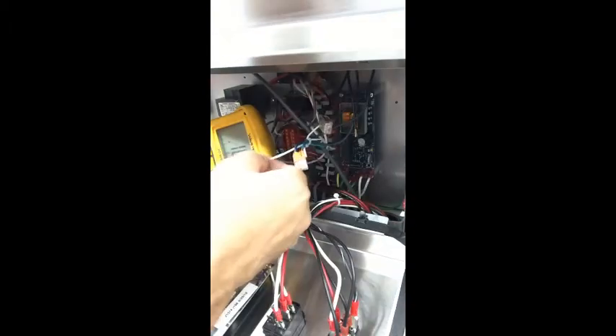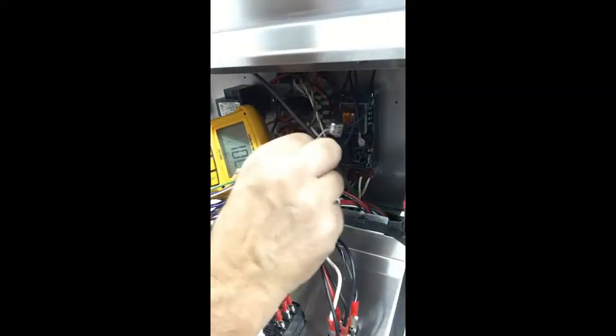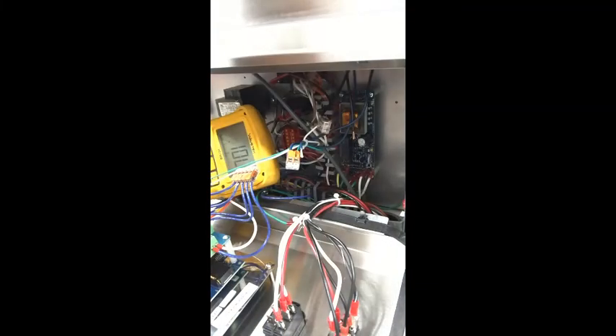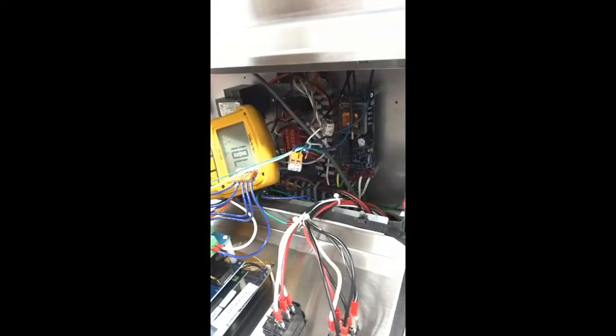Okay, so we're coming out on the green, hitting our blue wire, going to our switch, coming back on our black. We've got one switch right now working. We do need to come back and replace that other switch, but in the meantime, they can run safely with one switch, and we know what the issue is. Okay, so then come back later and change that switch.